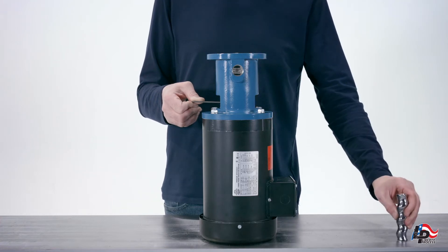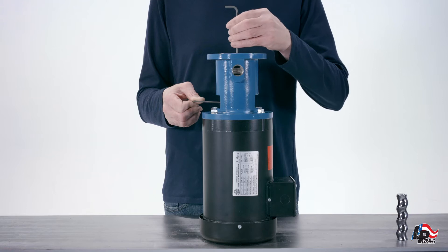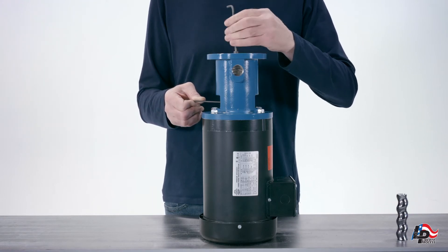Leaving the 7-64-inch Allen wrench in the stub shaft, use the 3-16-inch Allen wrench and place it into the top of the pump flex joint. Turn counterclockwise to remove the flex joint from the pump stub shaft.